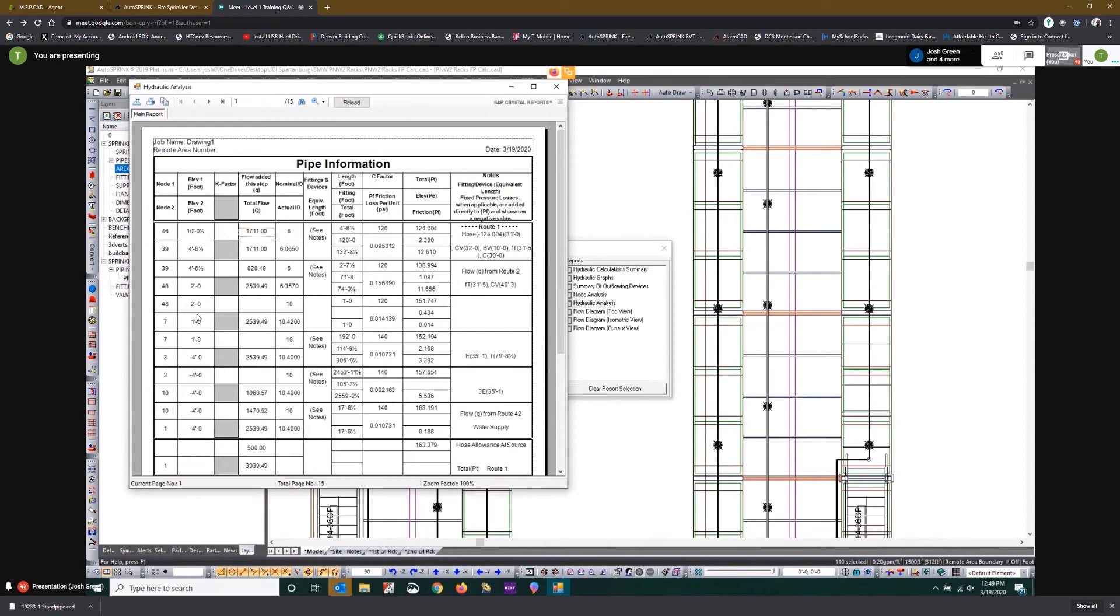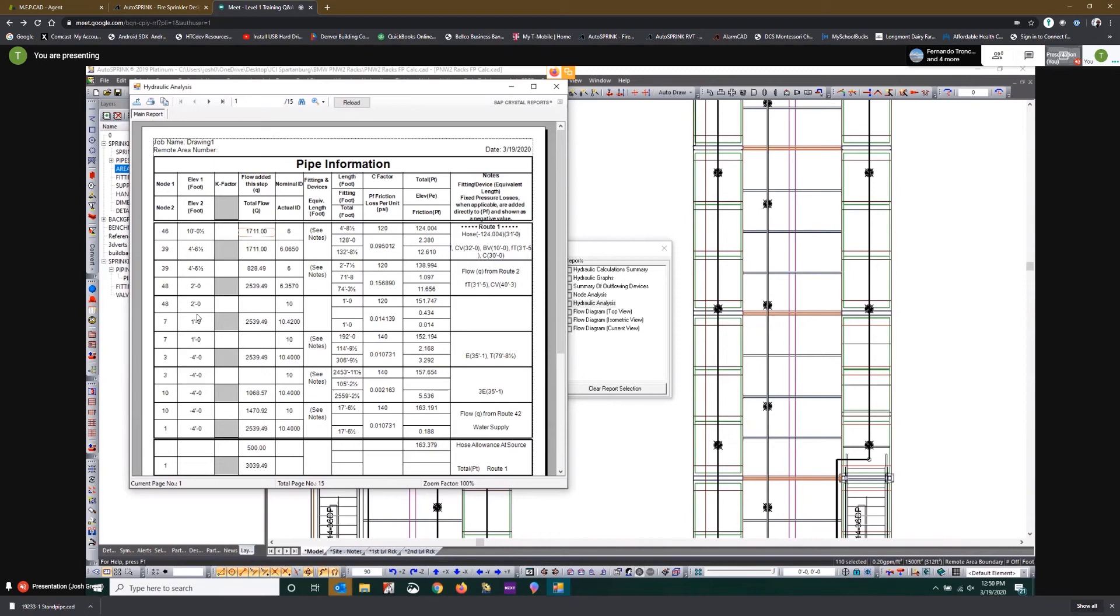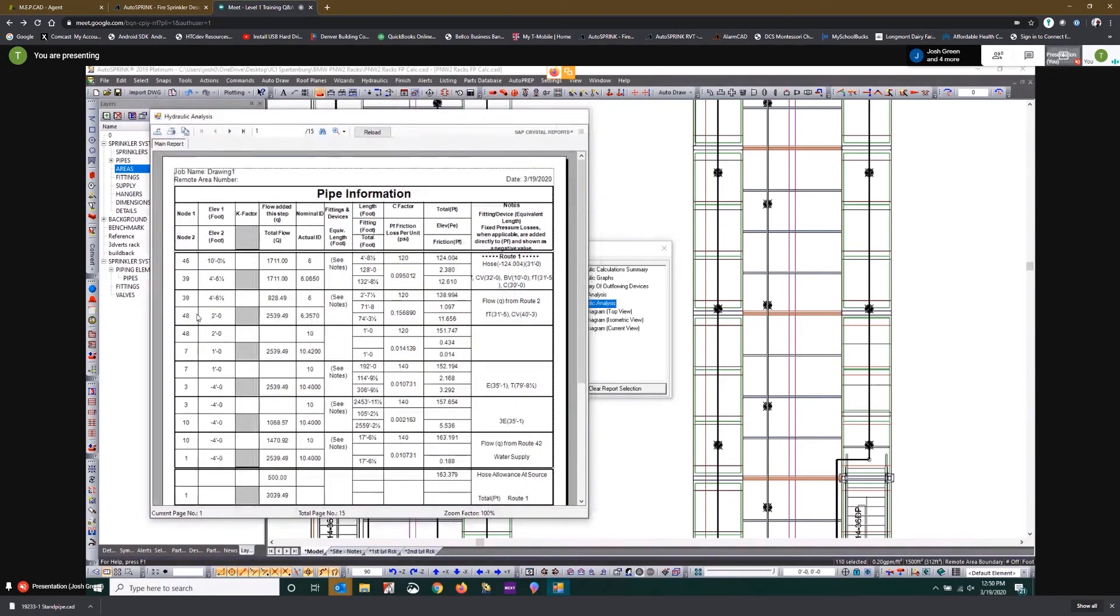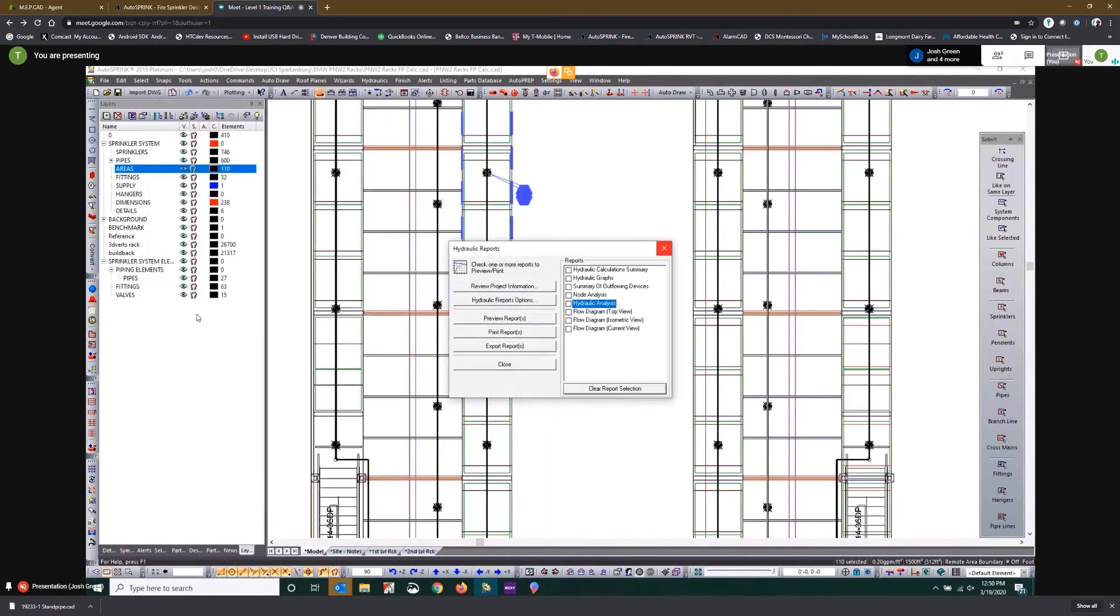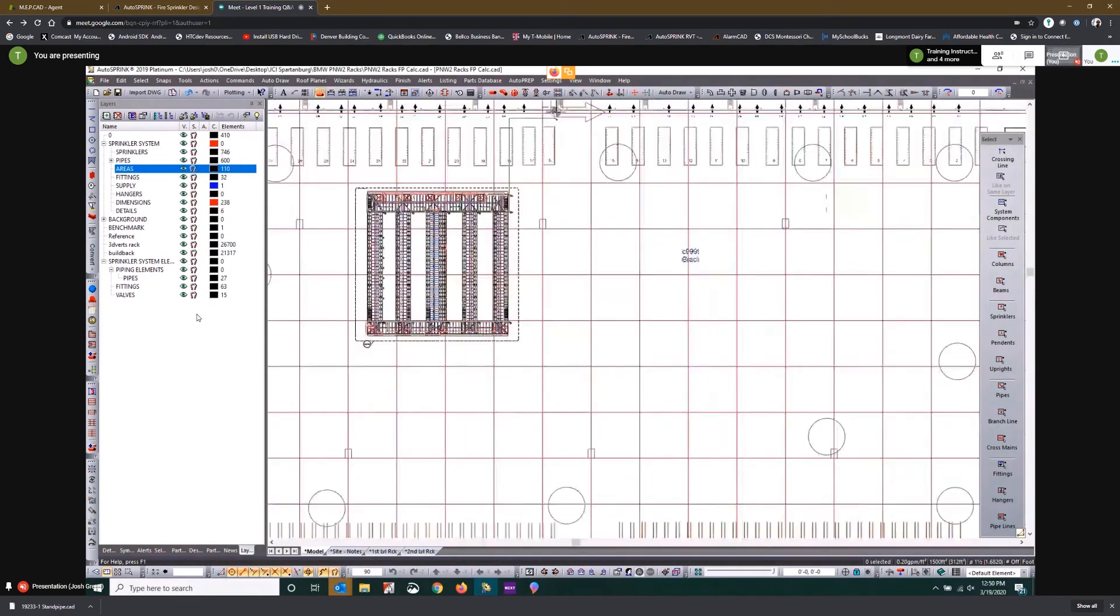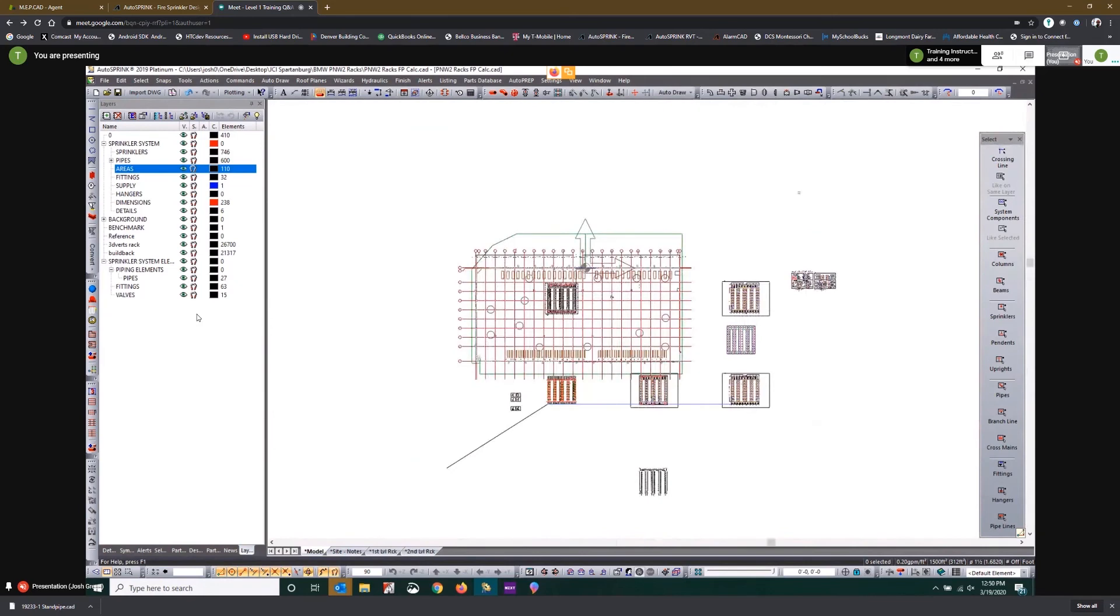We want to use it at the 1711. I just need to discern if 250 gpm of that is outside hose that they've accounted for as well. I may be double dipping on hose. Yeah, because this overhead is an ESFR system right? So they've got 1711, it's 17k ESFR, and of course they've got 250 gpm hose, but they want me to include 500 gpm in the rack demand. So the requirement here is to balance an existing ESFR overhead with an in-rack system? Yeah, I've only ever seen that requirement for paper storage.